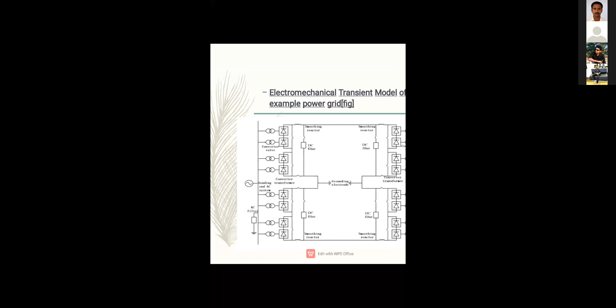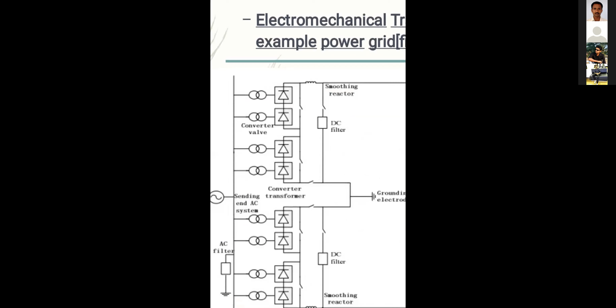We can see here first the sending end input is AC. Then here we have the DC filter. Then we have connected the ground. There are the converter transformer and smoothing reactor, AC filter, DC filter, reactive power compensation equipment, etc. The bipolar operation is carried out with each pole using a 12 pulse converter. The inverter side is controlled by constant turn-off angle. When the triggering angle of the rectifier side reaches the minimum, the inverter side is converted to constant current control.